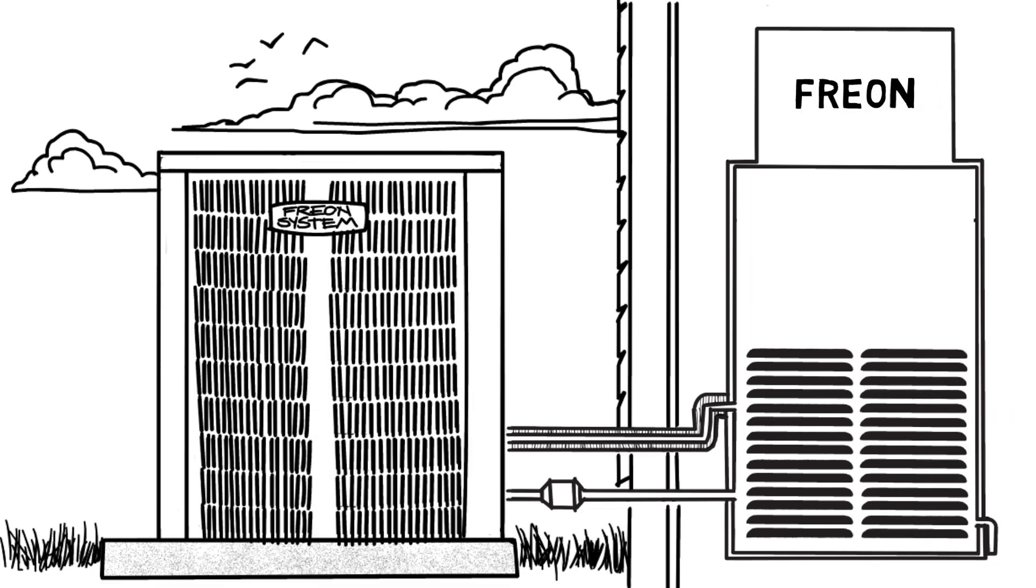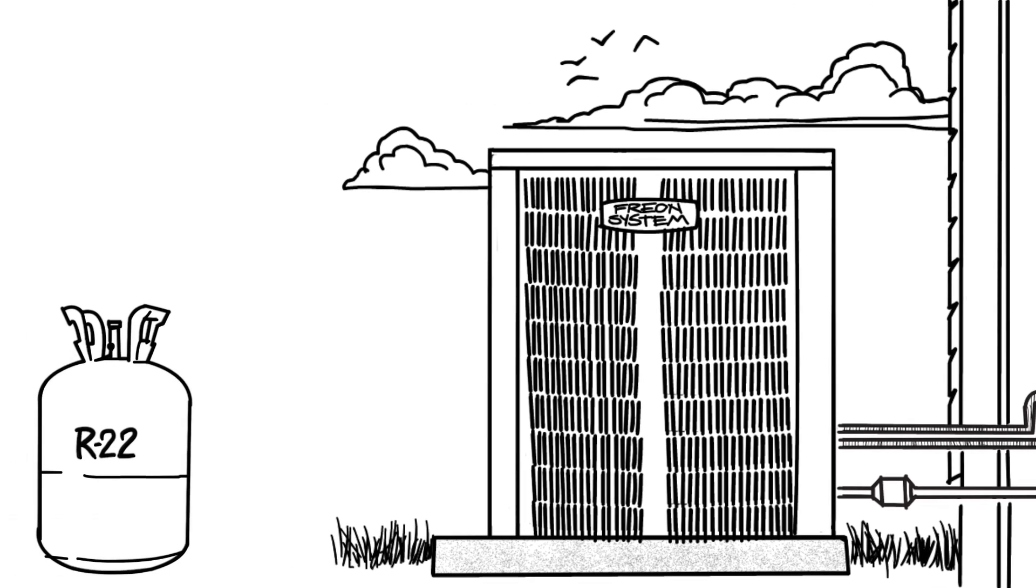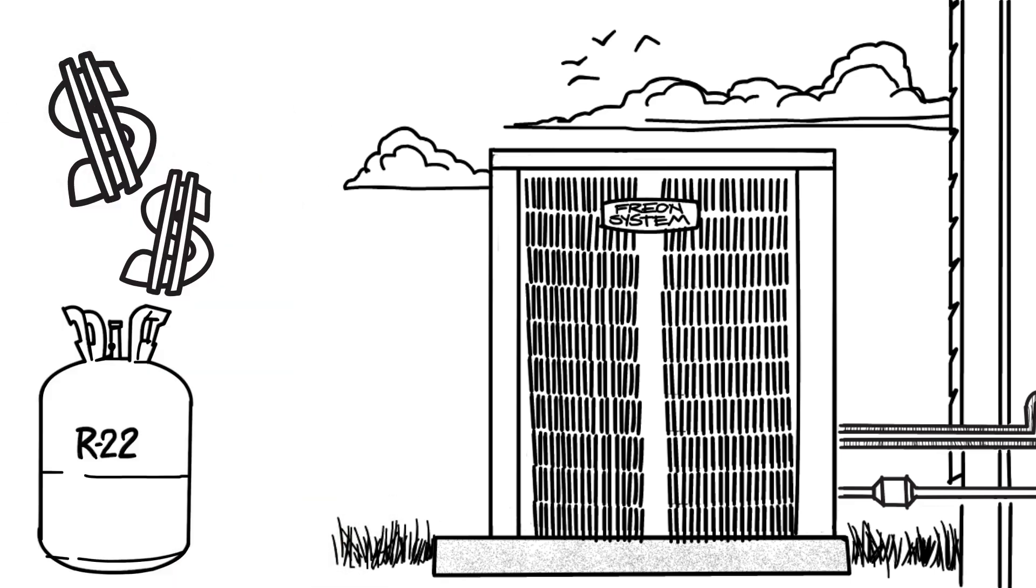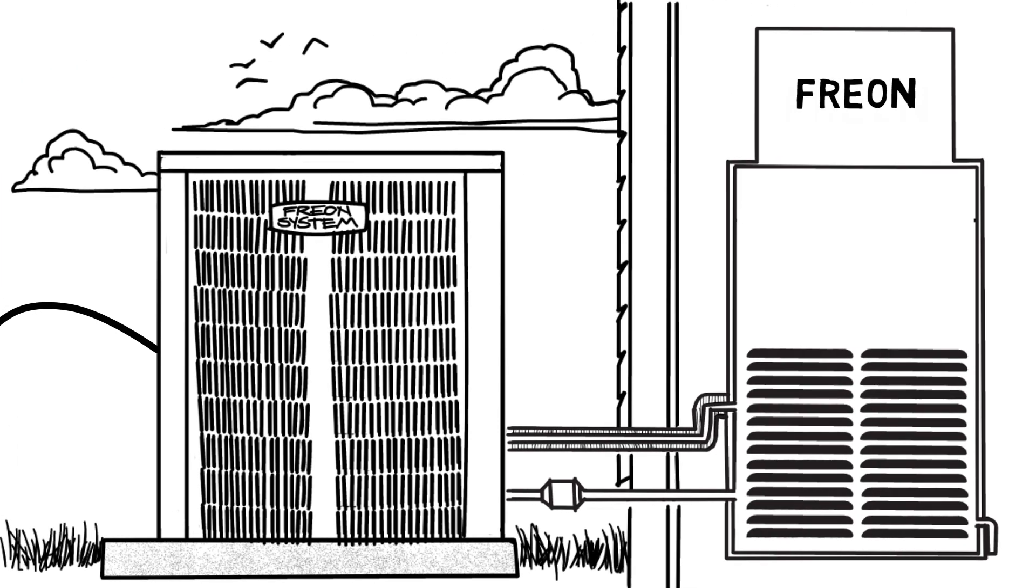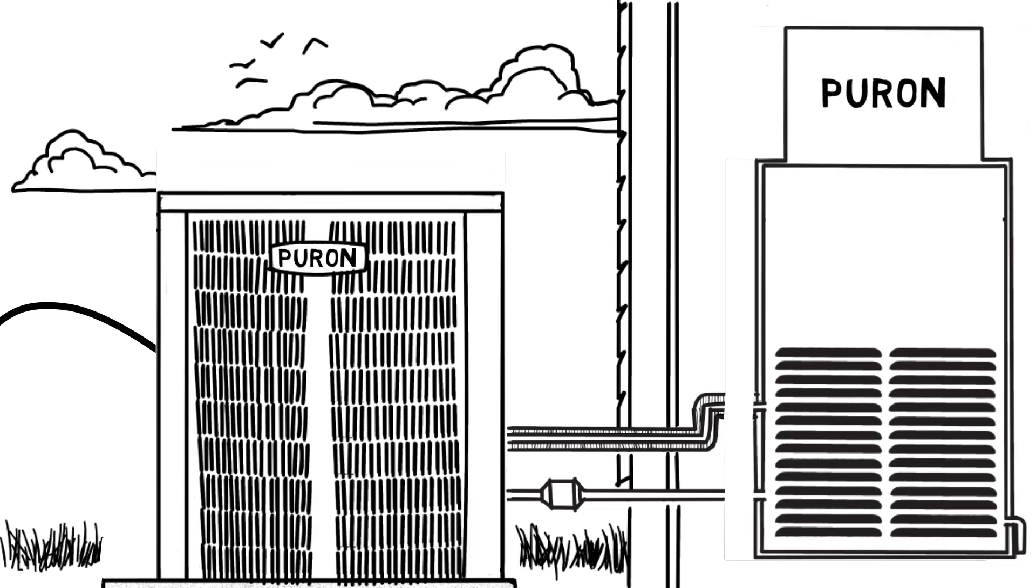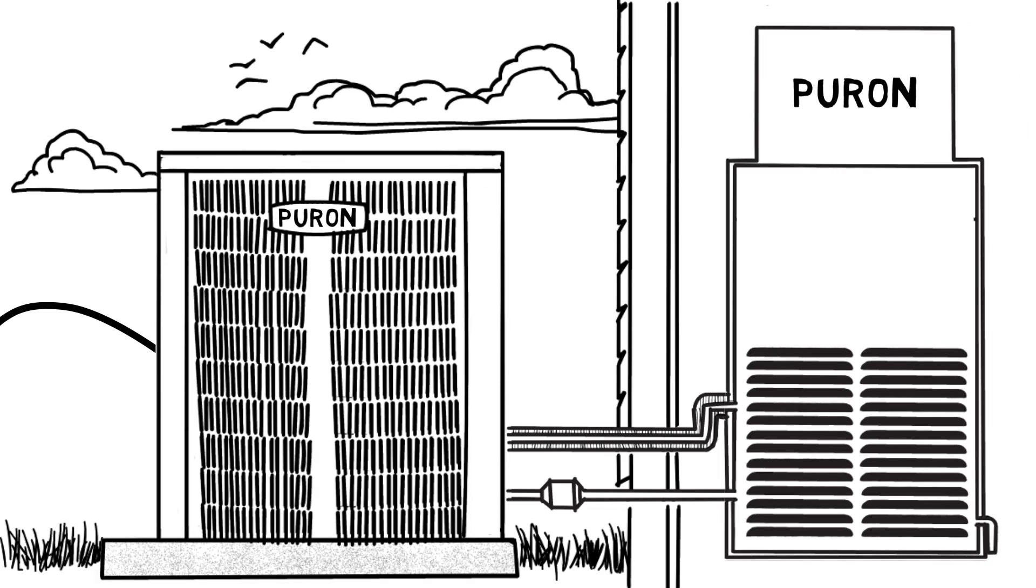Another common failure is the compressor, which is located inside of the condenser. These are typically available for Freon units. However, with the ever-rising cost of Freon, this repair could become very costly, since the whole system will need to be refilled with refrigerant. In this scenario, the homeowner may choose to replace the entire unit to a new Puron one to avoid the high cost of Freon refrigerant.